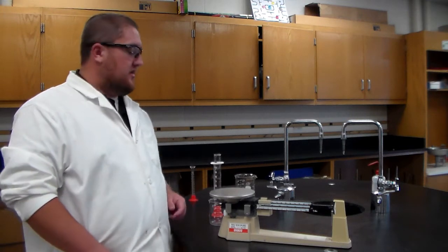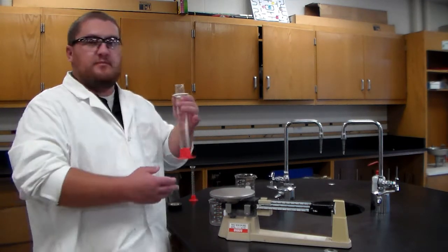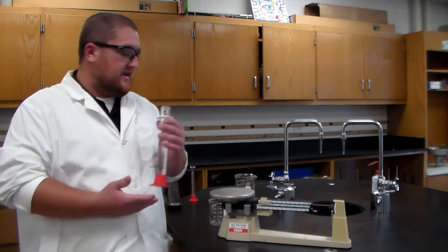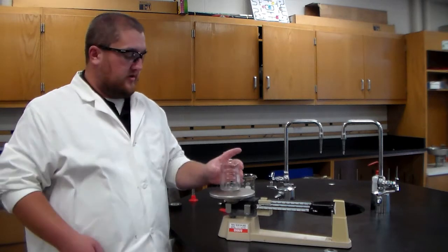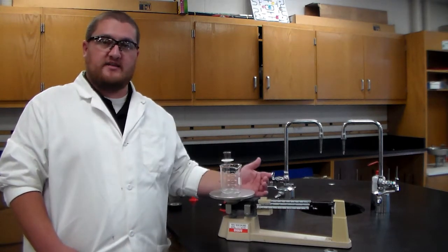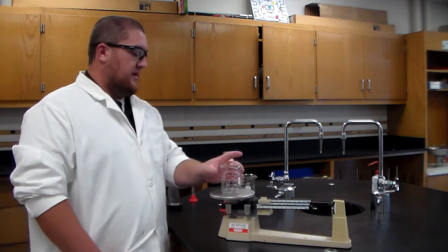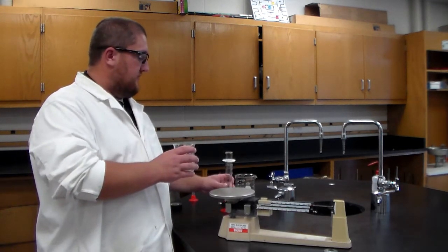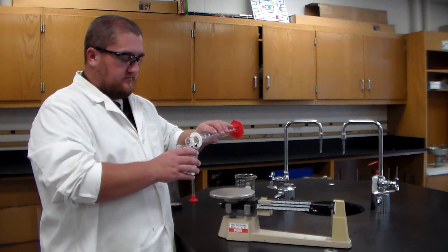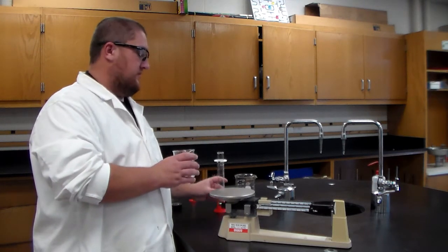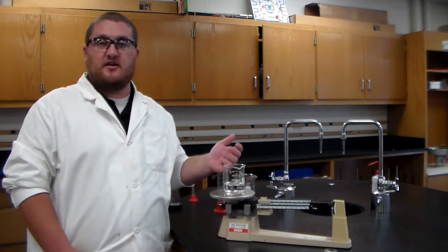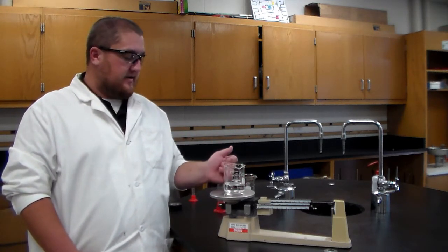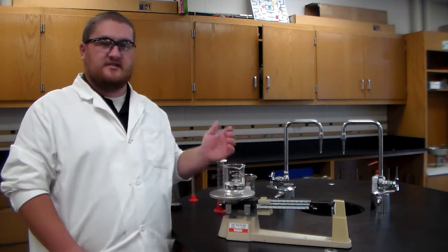Something to consider when you're measuring the mass of something that can't be directly set on the weighing pan is to use another container to measure it. For example, if I had a sample of water in a graduated cylinder that I wanted to know the mass of, I would then need to find the mass of the container that I'm going to put it in first. So I determine the mass using the riders. I would then pour the sample into my container. I would then measure the mass of the container and the sample and subtract out the mass of the container to measure the mass of the water.